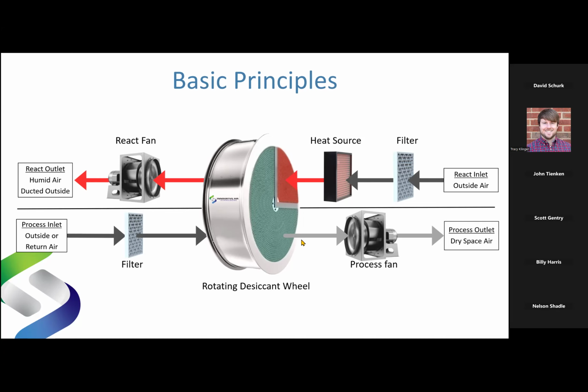Okay, leaving the wheel then is air that has been dehumidified, perhaps deeply dehumidified. Perhaps the air leaving here is at a fraction of 1% relative humidity, if that's what you need. Lithium battery manufacturing, for example, we're providing negative 80-degree dew points. That is incredibly dry air. You have to in those environments. Any environmental moisture in the air at more than a single-digit relative humidity in the space will react with lithium. It will create a corrosive response that combusts and you blow things up. You can't do it. Lithium battery plants use desiccants all the time. But the point is, it can be as dry as you want it to be. It doesn't have to be that dry. And what will determine how dry this wheel is and how much moisture it can remove, and the relative humidity or dew point that you can get down to on the process leaving side, is the heat source. The more heat, the drier the wheel. We'll come back to that in a minute.